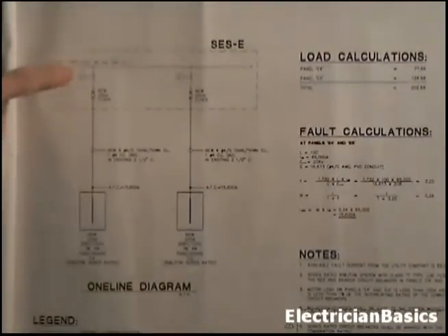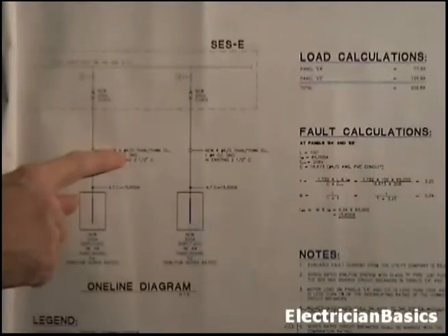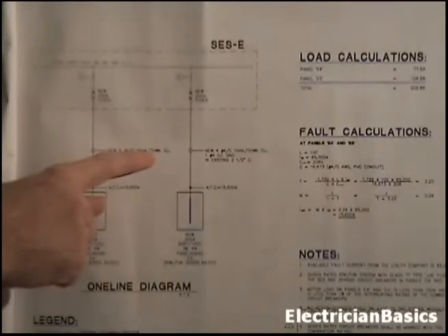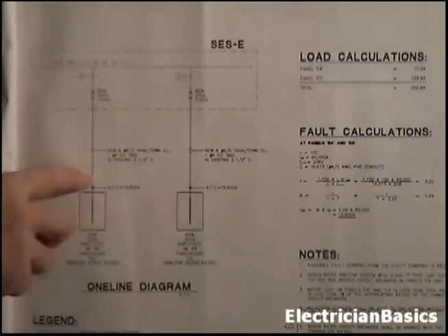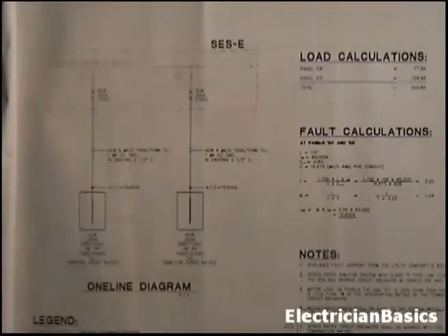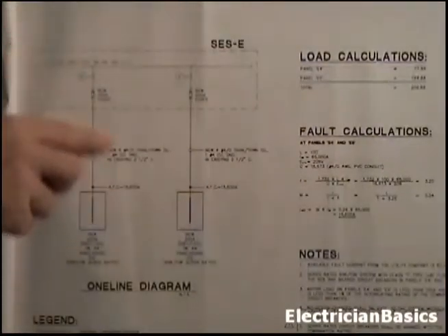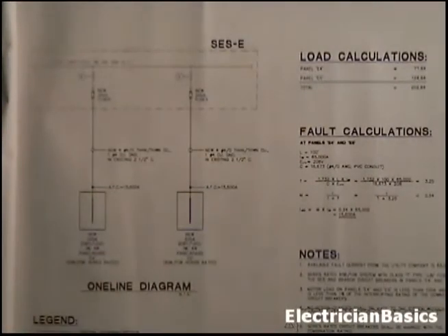Now these are at the SES. Now the panels will have a breaker in them. We come here, and this says new number 4 aught THHN, THWN copper wire with a number 4 ground, in an existing 2.5 inch conduit. So when this building was built, initially they put this conduit in underground, a PVC conduit. Now they got it close to that unit, and what the electrical contractor had to do was actually dig it up, and of course an engineering note, they left a plan of where they left it. Dig that up and then trench over to the panels and finish that out in the exact location where the panels were set. This is not a dotted line, even though it was underground.